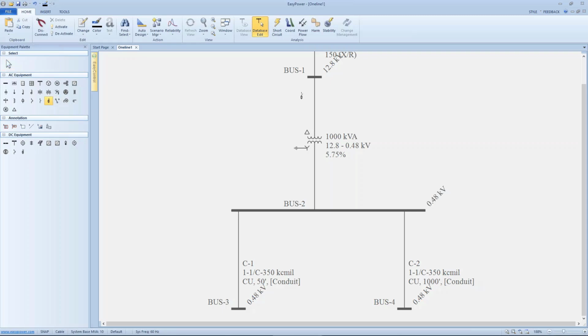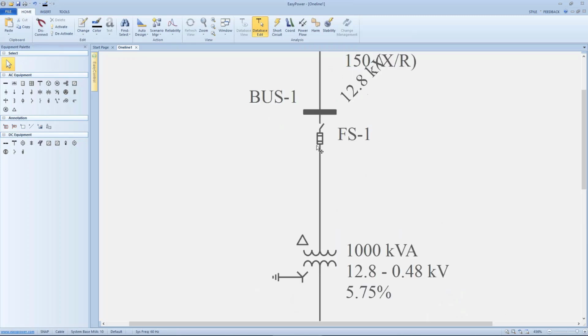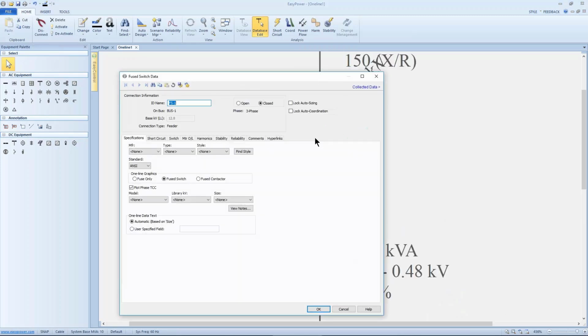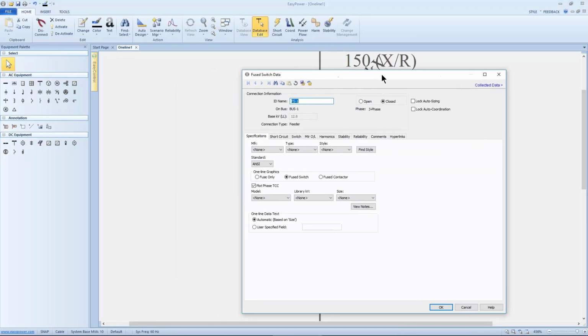In this case, we're going to put a fuse switch right below the utility bus here in line and click another time. He says the label on this fuse indicates this is an AB Chance. Now, this is the first dialog box that we've worried about, the manufacturer. Built in with the tool, installed with EasyPower tools, is a device library that includes 40,000 entries, so it's pretty difficult to find a device we don't have listed in the library.